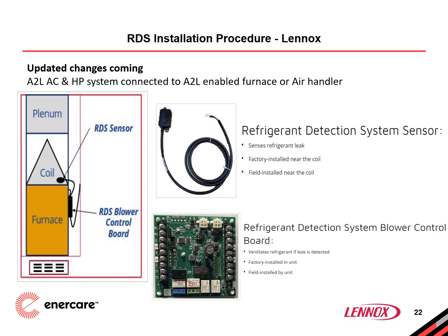The RDS consists of a few key components. One, an R454B rated sensor is installed near the evaporator coil, typically on a mounting bracket, and senses potential refrigerant leaks in the airstream. And two, the blower control board. That is integrated or installed to ventilate the area by running the blower when a leak is detected and ensures that any leaked refrigerant is diluted and moved away from enclosed spaces to minimize risk.